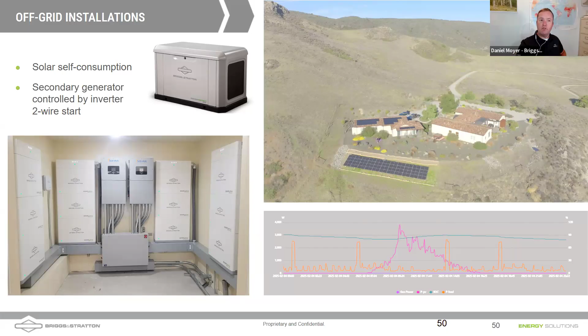Okay, there's a little bit of programming in the Briggs & Stratton generator in order to enable the two-wire signal to start. So, Andrew, I always thought that a generator always feeds power to a home, but actually you're always feeding power to a generator all the time. You have to feed power to a generator to keep its starting battery charged, to keep any cold weather accessories, keeping the engine warm and the battery warm, but also you're sending power to a generator so the generator knows when grid is there or not there. And if it sees that grid is not there, it's going to start itself up.